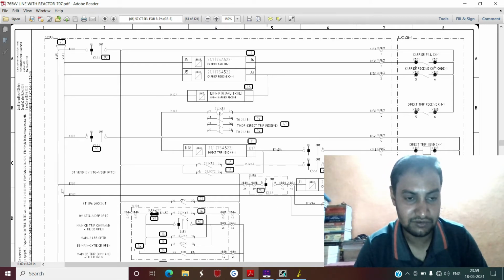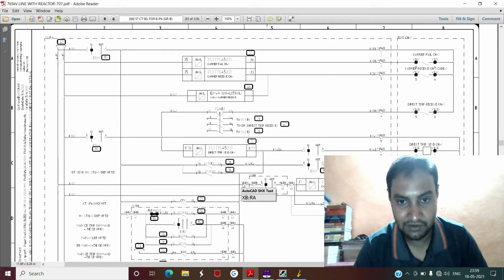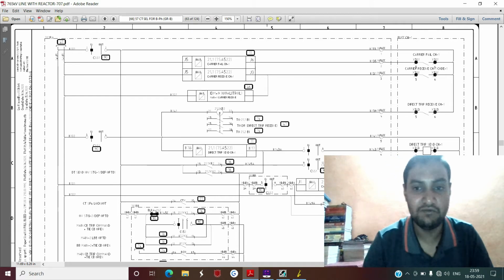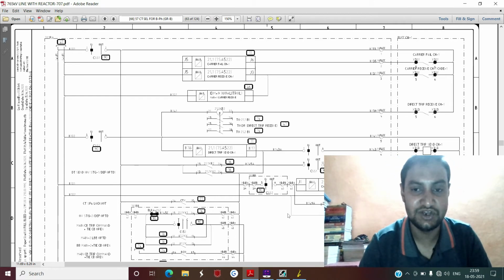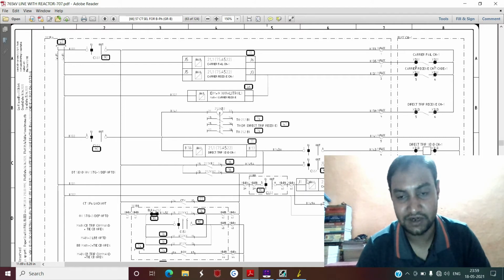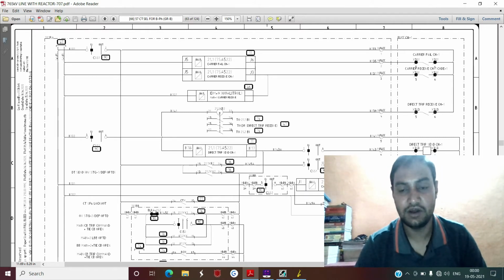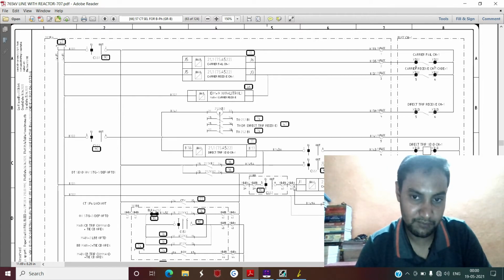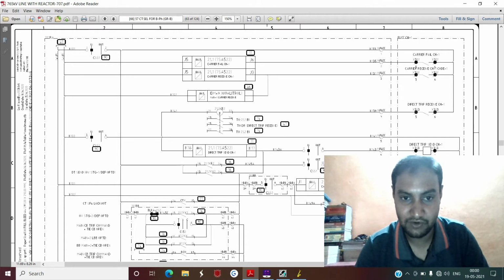So that means your switch will generally be in the 'in' condition. So this is DC positive, it is coming here, it is coming here, and now it is available up to this terminal J1. But what we want is that we have configured this J1, J2 as active with voltage. So that means we want across the J1, J2 terminal a voltage difference, or a DC voltage, of 220 volt. But right now we are only having this 110 volt here, the positive. So we also want 110 volt negative here.